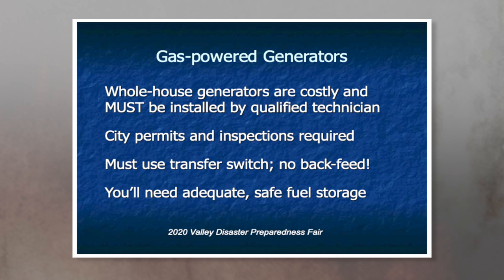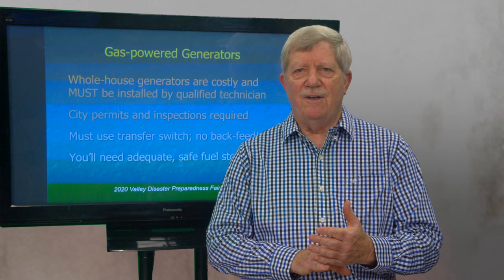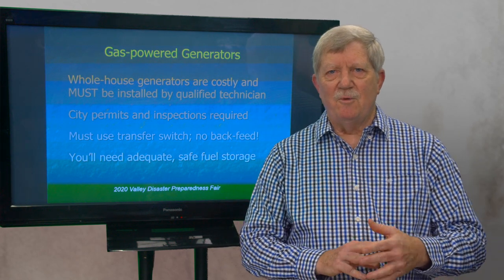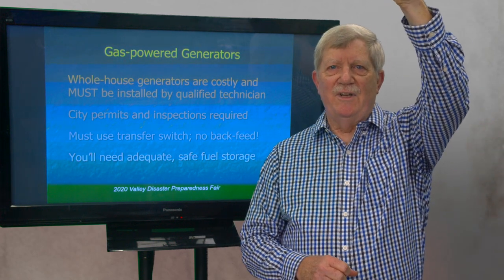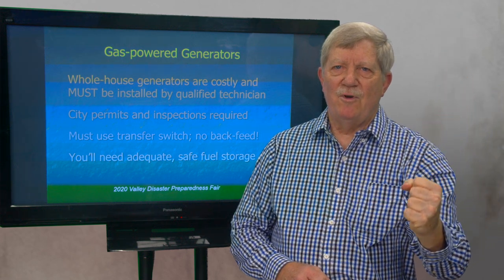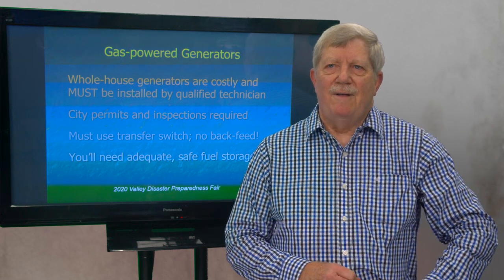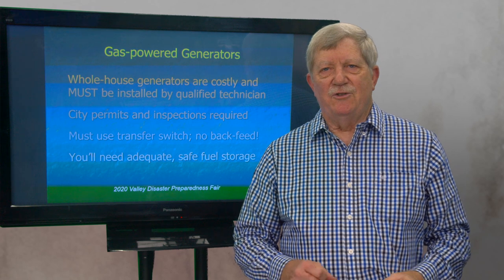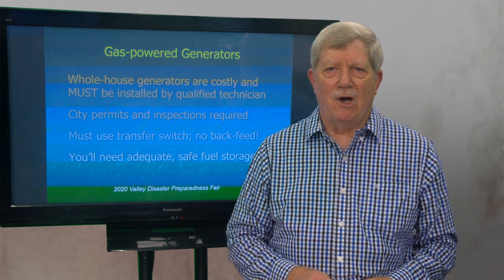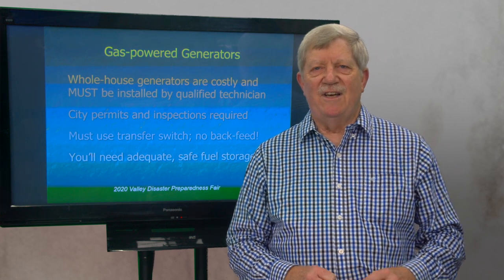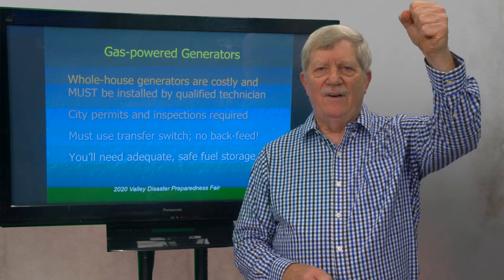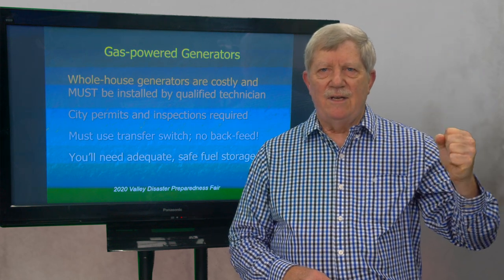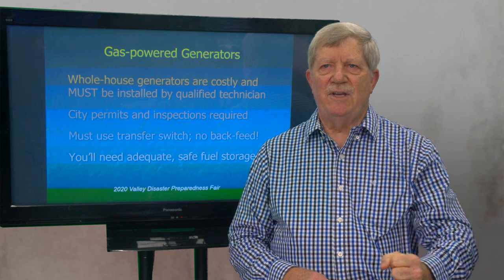But you need permits for that, inspections. It has to be installed by a qualified technician. You must use a transfer switch. Think of the old horror movies where some mad scientist is pulling this big knife switch from one position to another. That's actually a transfer switch. Yours may not look quite as macabre, but that's what it does: it makes sure the power cannot go to both the line and the generator at the same time.